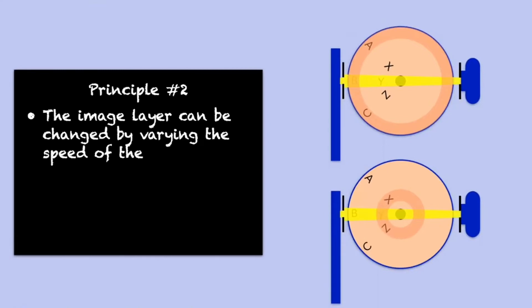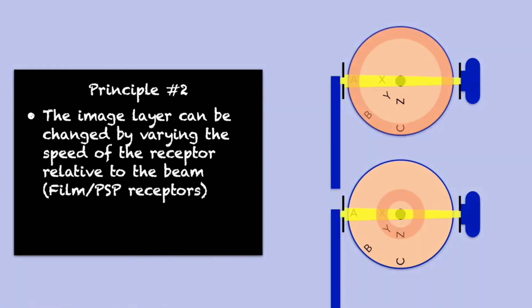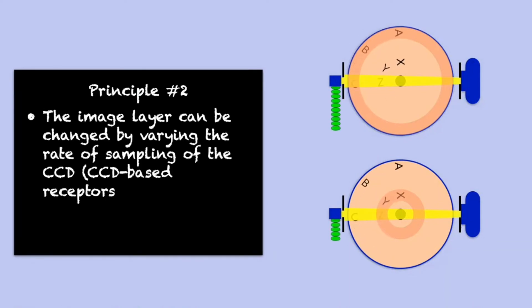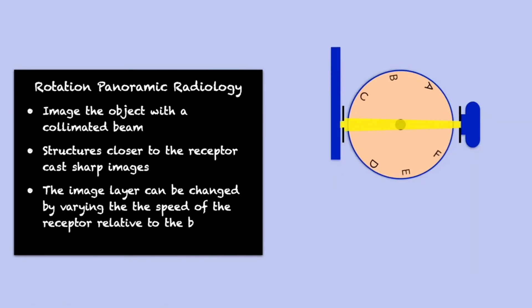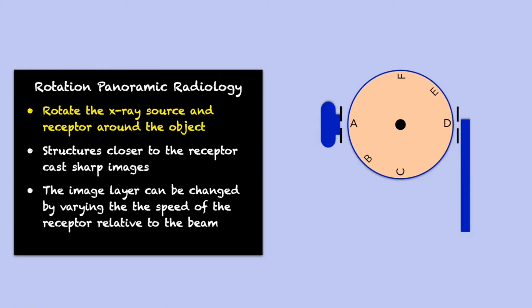So principle number two of panoramic imaging: the image layer can be changed by varying the speed of the receptor relative to the beam. This holds true for film and storage phosphor receptors where there is a physical movement of the receptor past the collimator. In CCD-based panoramic machines, a linear array of detectors is affixed behind the collimator and does not move during the exposure. In these units, changes in receptor speed are simulated by varying the rate of sampling of the CCD receptor. To accomplish panoramic imaging, we image the object with a collimated beam. Structures within the image layer will cast sharp images, and we can change the location of the image layer by varying the speed of the receptor relative to the beam. Note that the same objectives can be achieved by rotating the X-ray source and receptor around the stationary object.